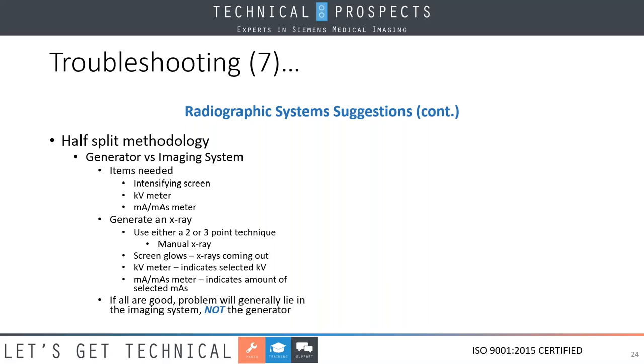What I want you to do is generate a 2 or 3 point technique, which is known as a manual X-ray. In other words, you're setting the KV, you're setting the time, minimum. And you're going to look at three things. The screen glow, that's important because now you know your tube's making X-rays. The KV needs to indicate what you selected. And the mAs or mA meter needs to indicate the same thing that you selected.